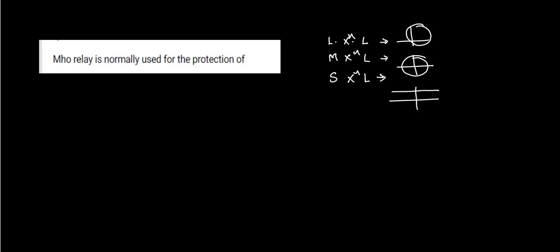First question: which relay is normally used for the protection of long transmission line? Whereas impedance relay is for medium transmission line, whereas reactance relay is for short transmission line. If you see the mho relay characteristic, it passes through the origin. For the medium transmission line, it has a circle centered at the origin, whereas for the short transmission line you have a line parallel to the x-axis.